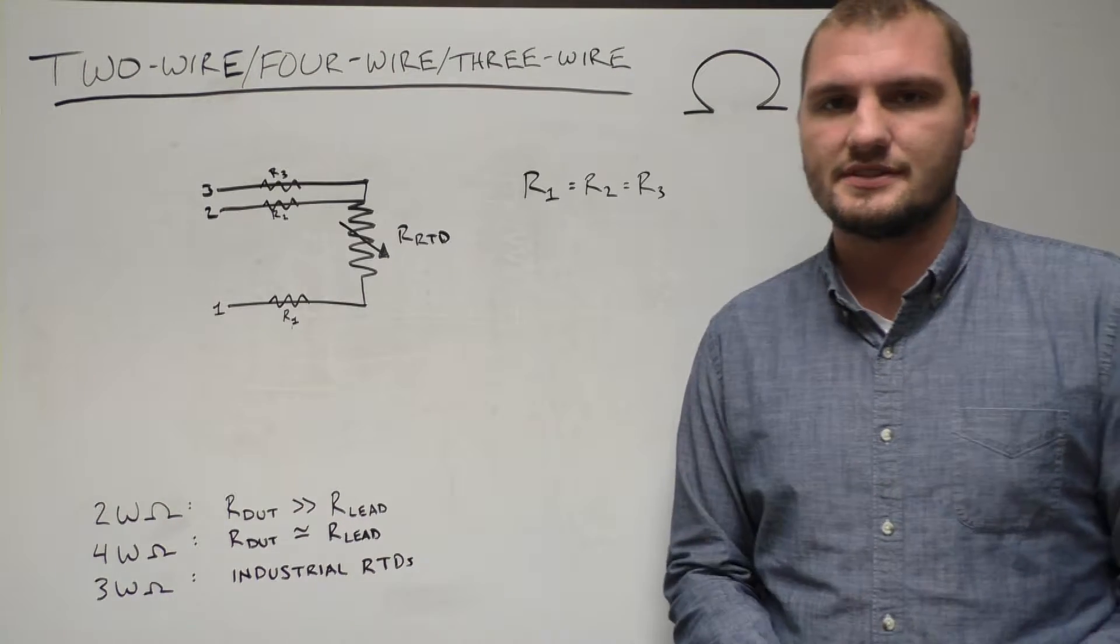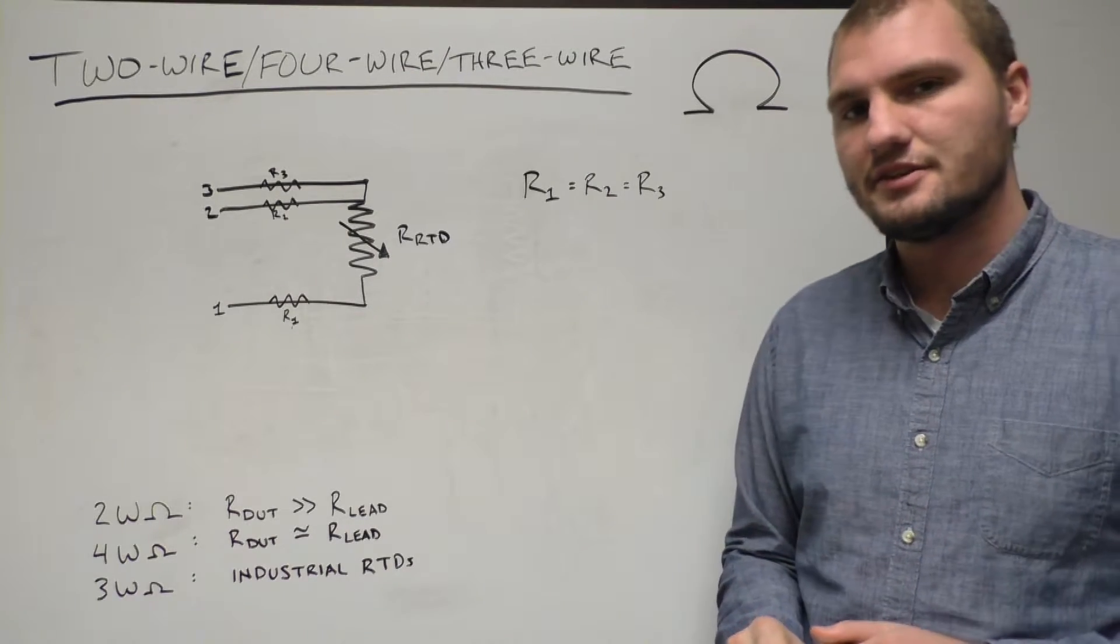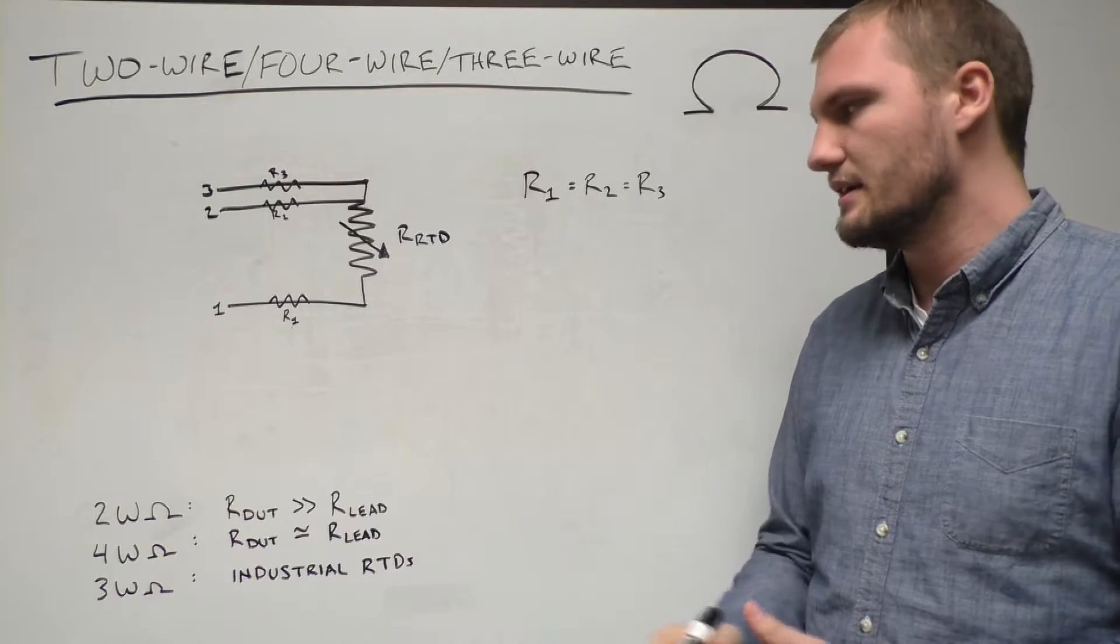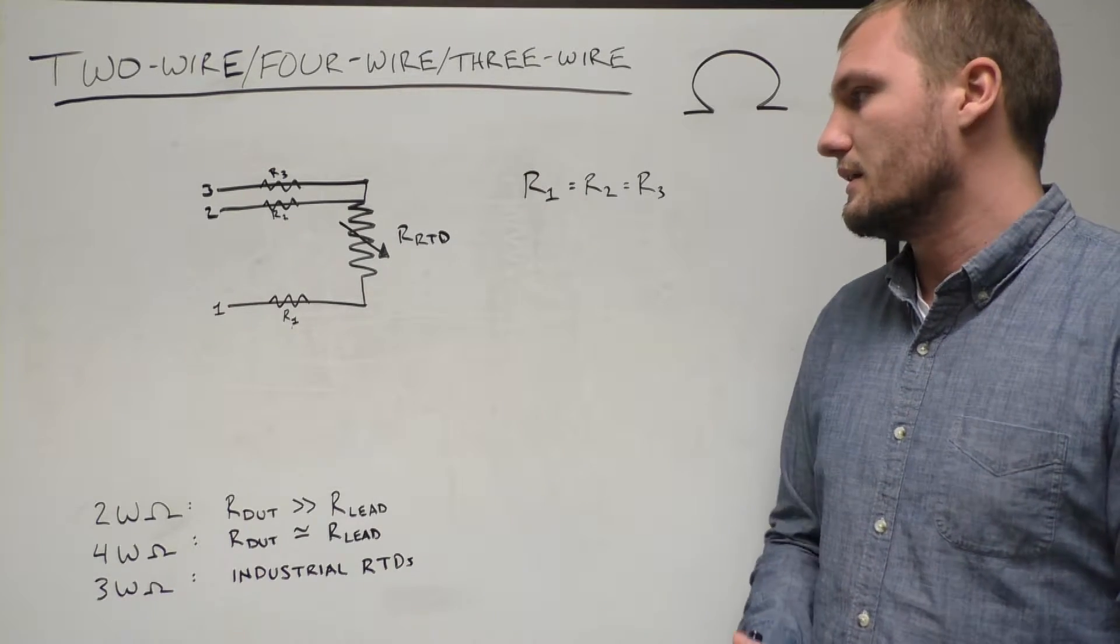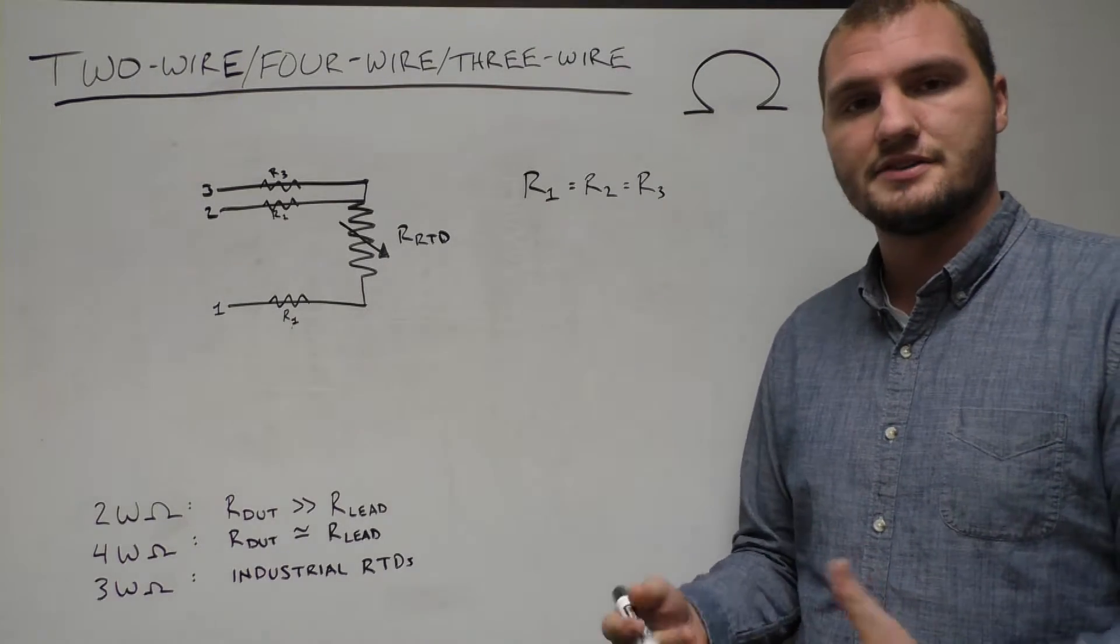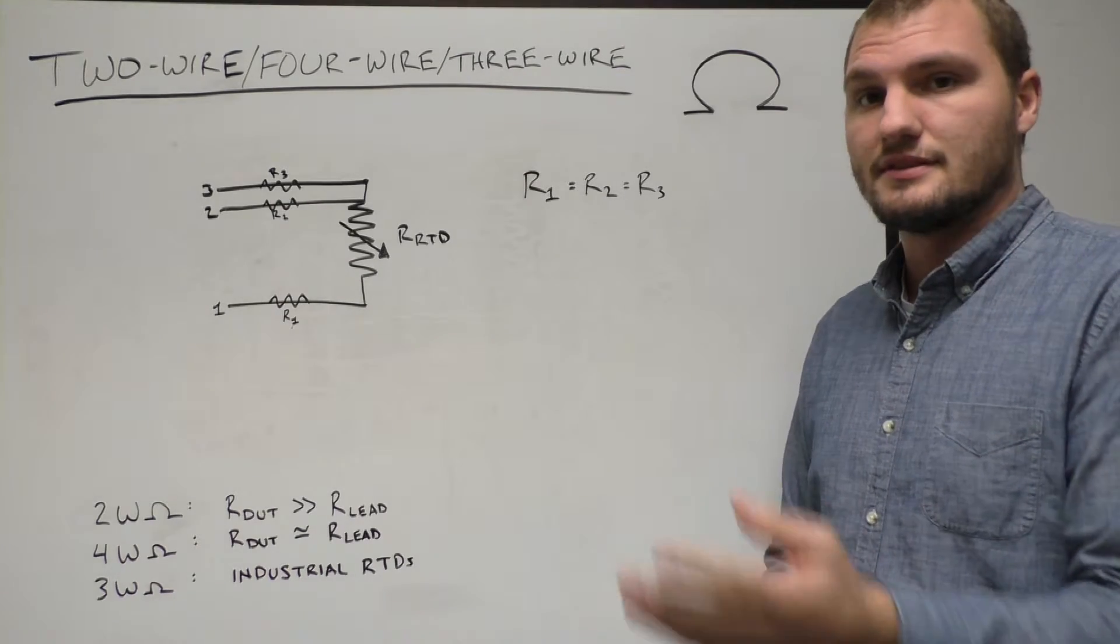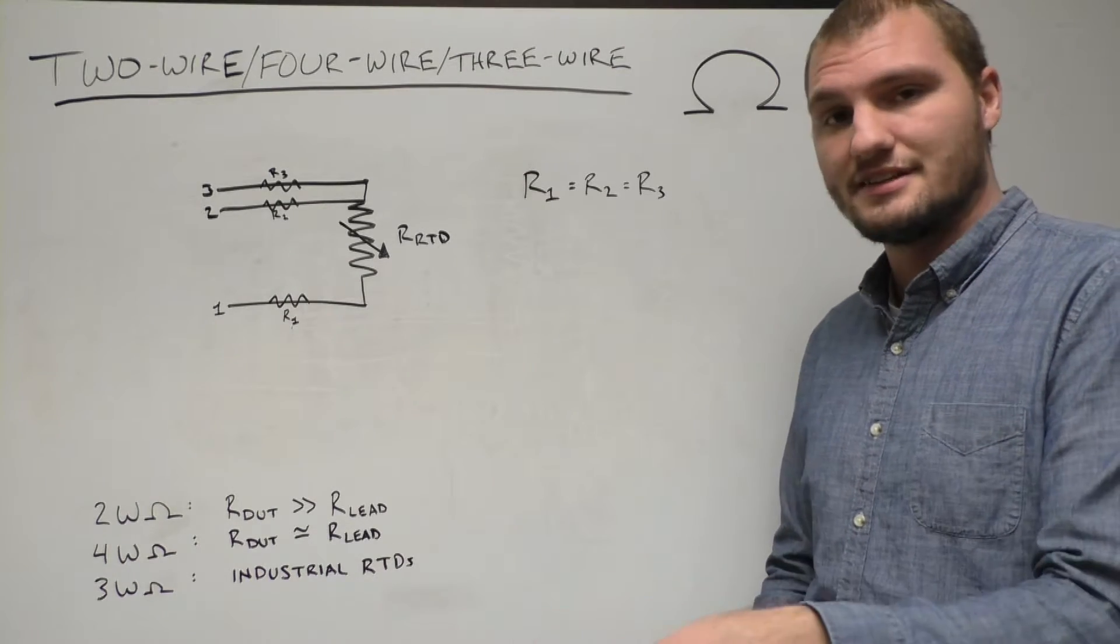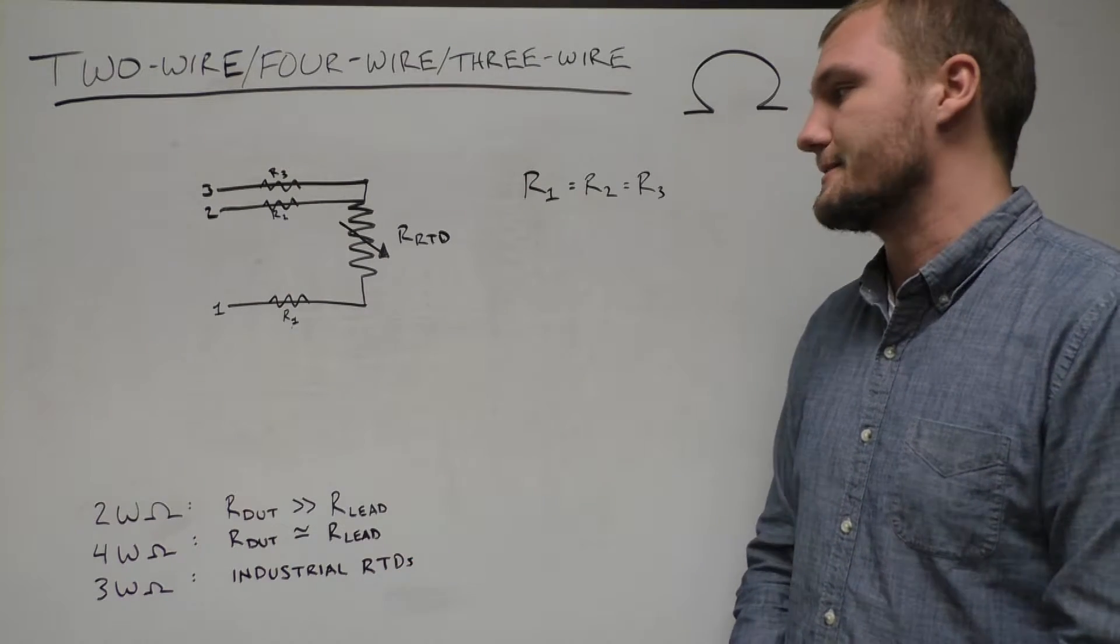The third resistance measurement technique is 3-wire, and this isn't commonly used for typical resistors, it's more often used for industrial RTDs. This method is similar to 4-wire in that it gets you that same accuracy for low resistance devices, but it uses 3-wires rather than 4, so there's less connections and slightly less cost in producing. So that's why it's fairly popular in industrial RTDs.